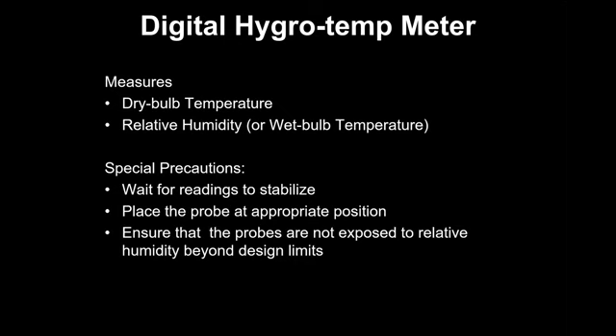And there are a lot of loggers available, because of this requirement, now that the HVAC load is going up. Loggers for temperature and RH are available at as low as 2000 rupees, 2500 rupees, where you can place them wherever you need, and you can have 24-hour data which can be transferred to your Excel sheet for analysis to see how the temperature and humidity vary along the day and night. So we do it while we are doing studies for the cooling tower, or sometimes even for the call center, the data center or server rooms, where the criticality is there.